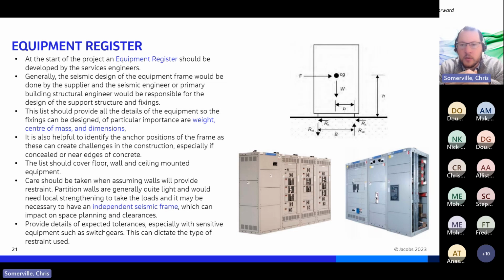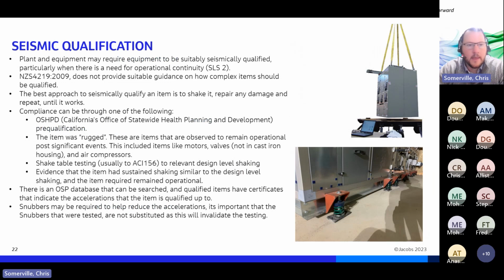Any equipment you're specifying, if there's anything unusual like tolerances, can be an issue. Some of the switchgear we do in the power industry has very stringent tolerances, like 1 to 2 mil movements, which needs to be factored into the restraint and support design. So if you can think of any of those, just let the engineer know.